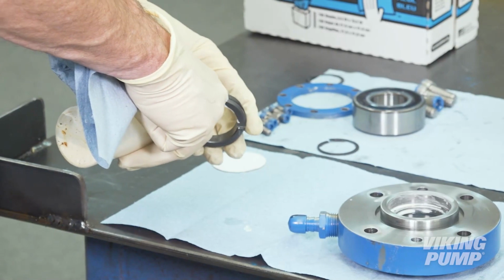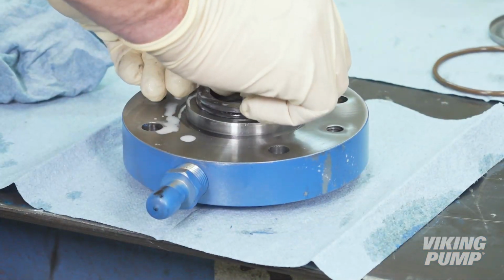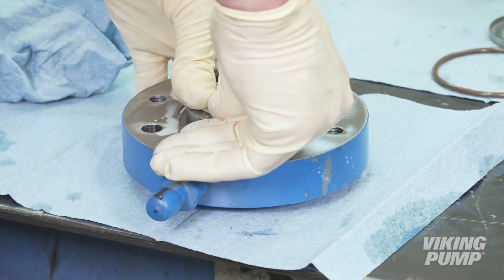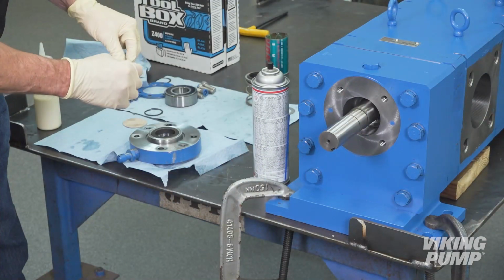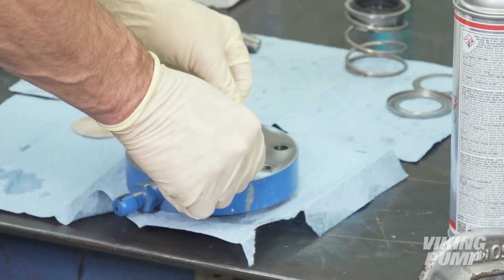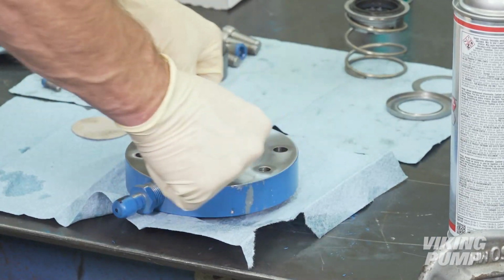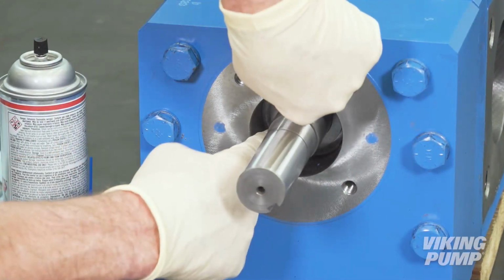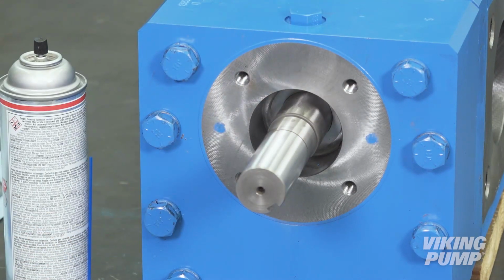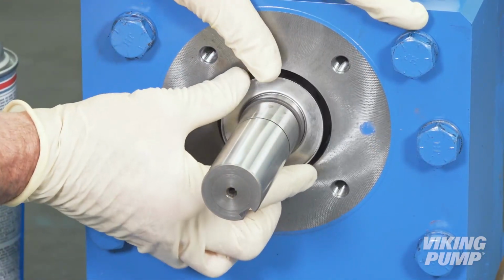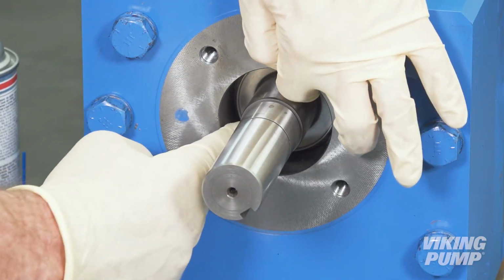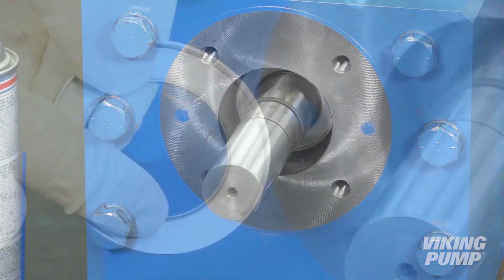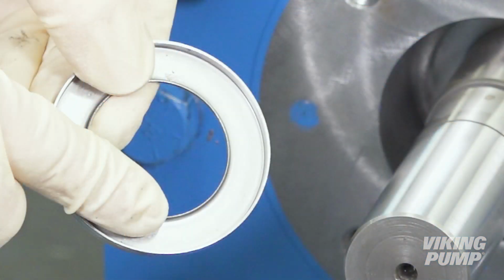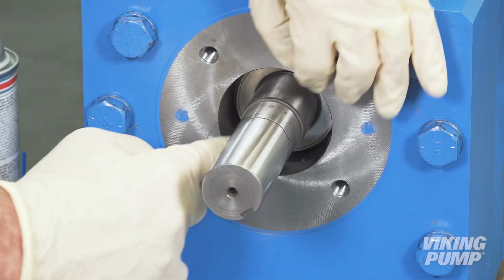Coat with P80 lubricant and install. Apply O-ring grease to the seal holder O-ring and place in the groove. Place the seal washer onto the shaft, making sure that it is fully seated against the snap ring that was previously installed. Install the seal spring guide, making sure that the spring guide is fully seated against the seal washer with the cupped section of the spring guide facing outward toward the motor end of the shaft.